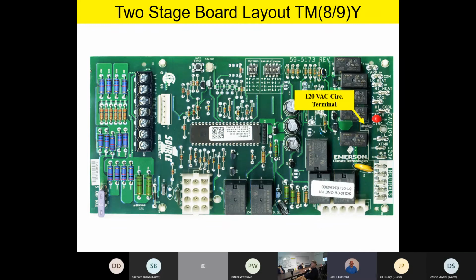Right below that, we have a 120-volt terminal we call CIRC. That's the 120-volt output to the motor all the time. Remember, a high-efficiency ECM type motor is going to have power to it all the time, and that's where we do it with that 120-volt CIRC terminal. Right below that, we have a 120-volt input to the board for all of our high-voltage components. The power coming from the power source into the furnace will hook up to L1 on the board right there.